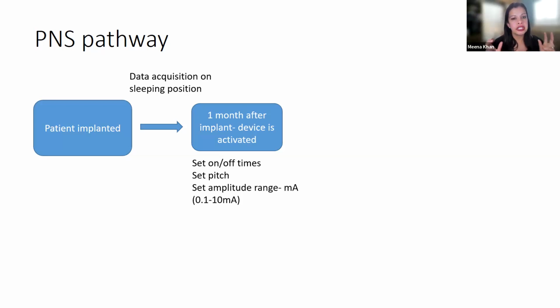And then we'll go over these steps in more detail in the upcoming slides, but just in general, in that activation appointment, we're going to set the time therapy turns on and turns off. We're going to set the pitch, which is the level the patient has to be below for therapy to kick on, and then the amplitude range, or the strength of stimulation range, which is measured in milliamps. And this can be anywhere from 0.1 to 10 milliamps, and there's a min and a max. Again, I'll go over that in more detail in the upcoming slides.